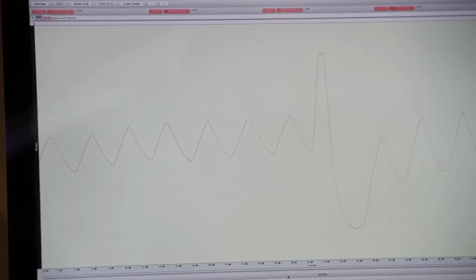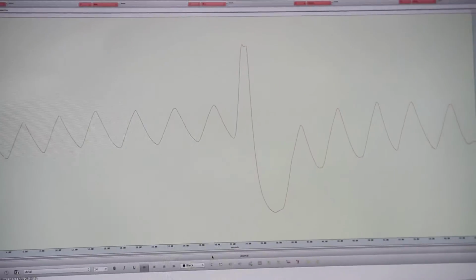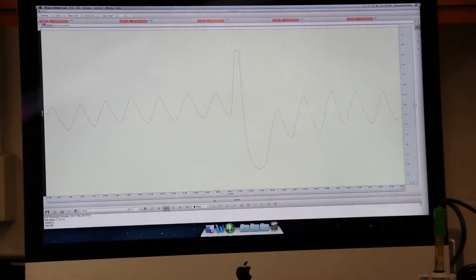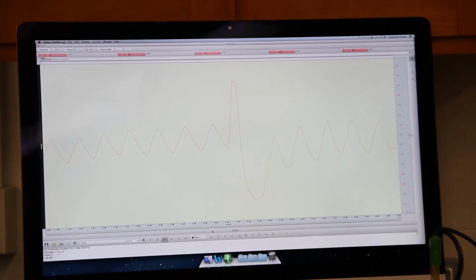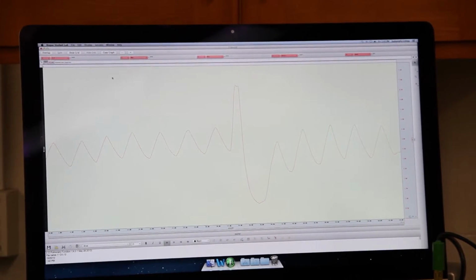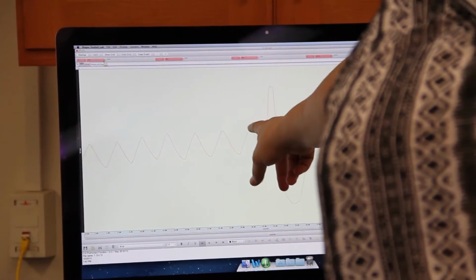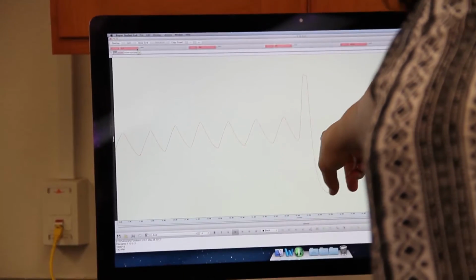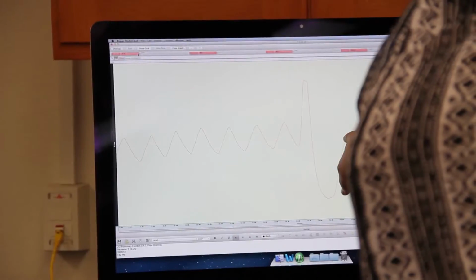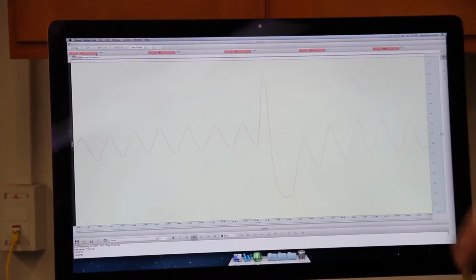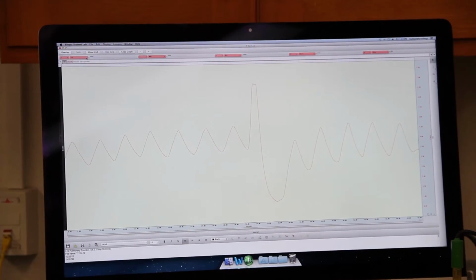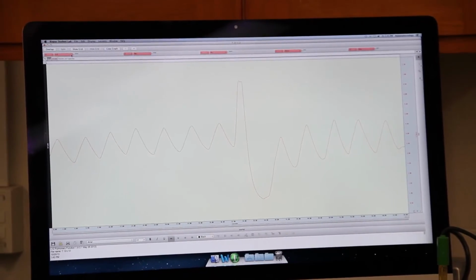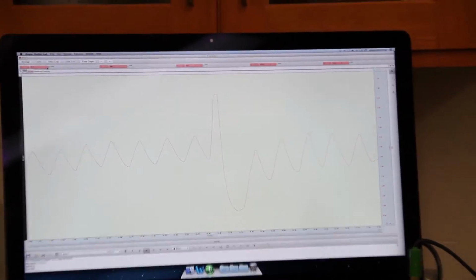Okay, so the lab manual clearly tells them how to do the measurement. One thing though, as a TA, when you're walking around, watch how they measure. If they use this peak that's directly in front of this, they need to use the same top and bottom of the tidal volumes for all their measurements. Because if they use this one to go to the peak, and then they try to use this one, they have different baselines. Okay, so when in their data analysis, if you walk up and it just doesn't seem like it makes sense, that's typically what happens. They're using different points, and so they'll get one that's really large and one that's really small that you're not expecting.